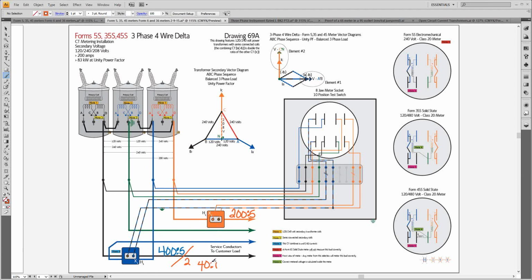And so again, this is the common way we did it, is have one phase going through one direction on the polarity side, the other phase going on the non-polarity side, and this is the only way I can wire it to make it so the current that flows in this CT will add together from these 2 phases. If I try to put them in the same direction, they'll subtract from each other. So this is the way it has to be done in order to get the wiring right. Again, this is the high leg, and it only has a single wire going through the CT at half the ratio.